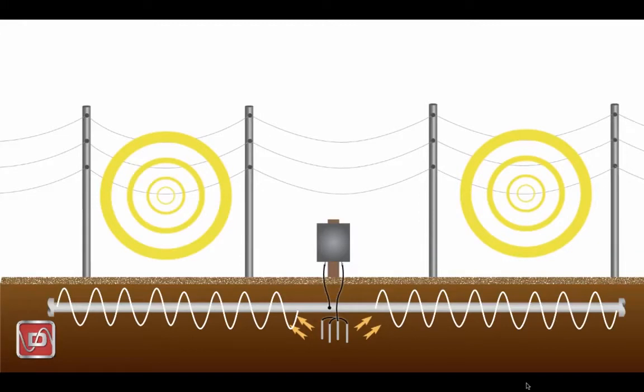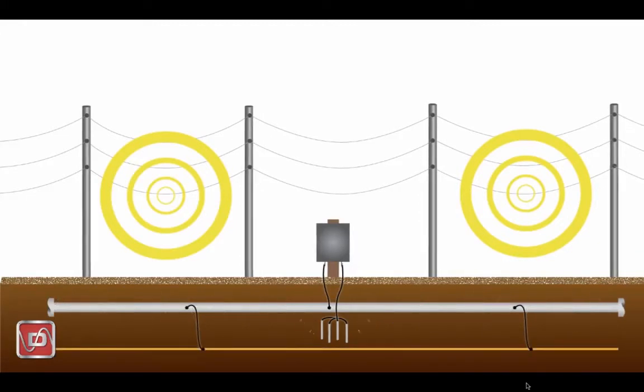We now have a pipeline that is safely grounded and is mitigating the induced AC off of the pipeline. Unfortunately, direct bonding zinc, like we've done here, will negatively impact your cathodic protection system. You will likely see an effect upon your CP system voltage levels and current will be exchanged. This is where the decoupler comes in.